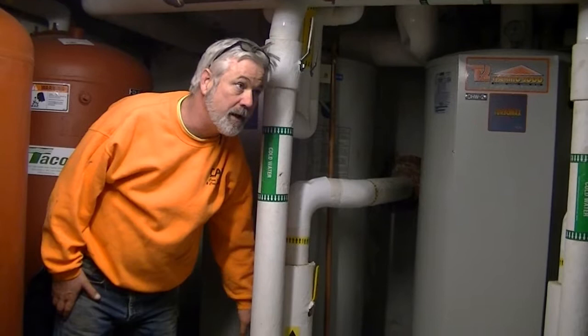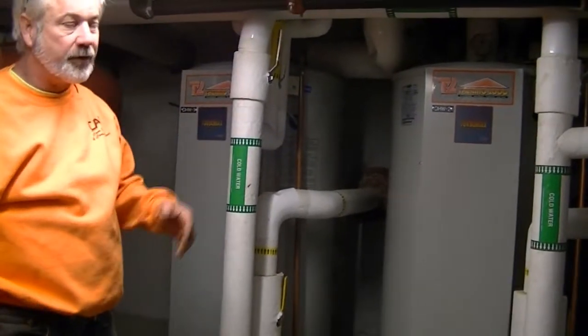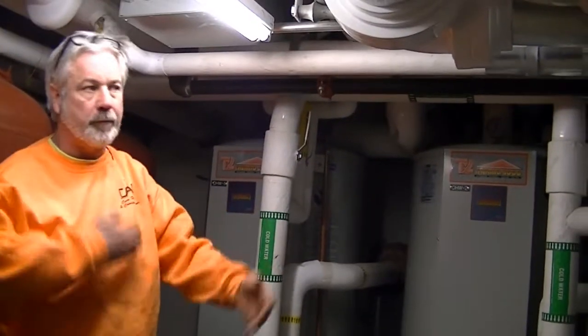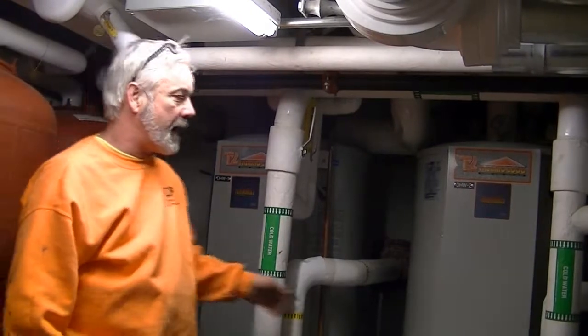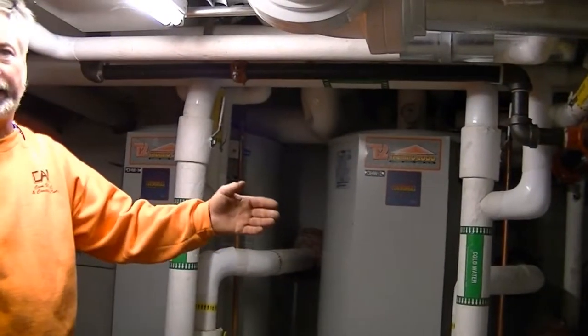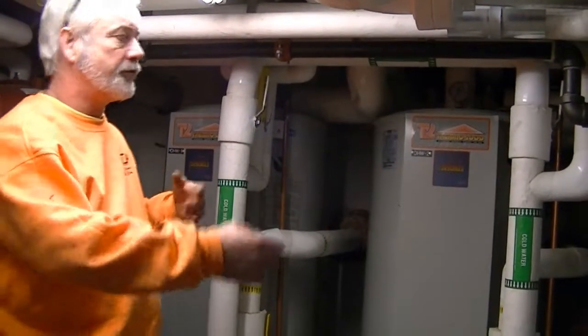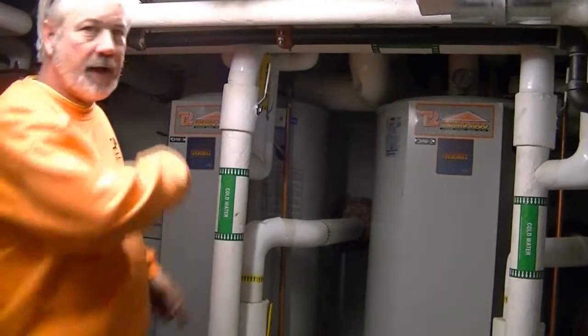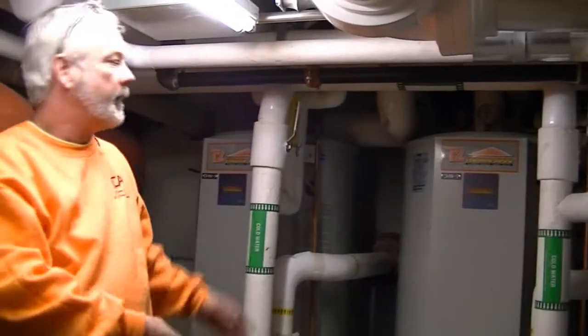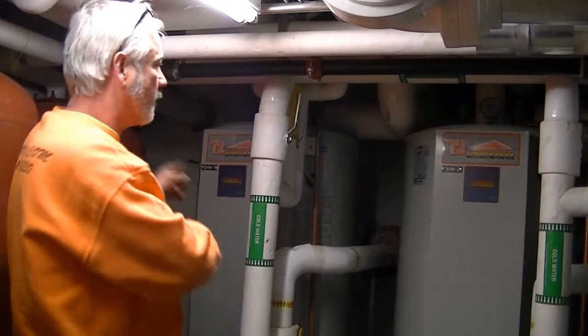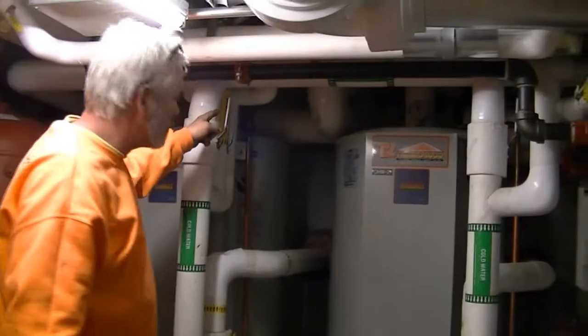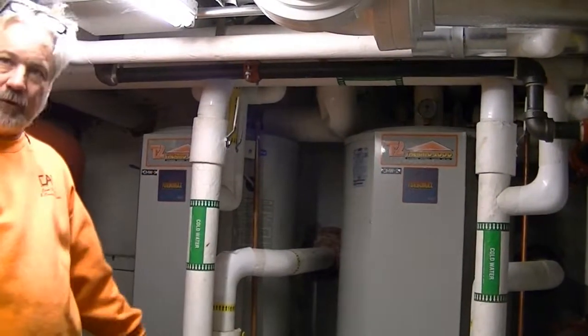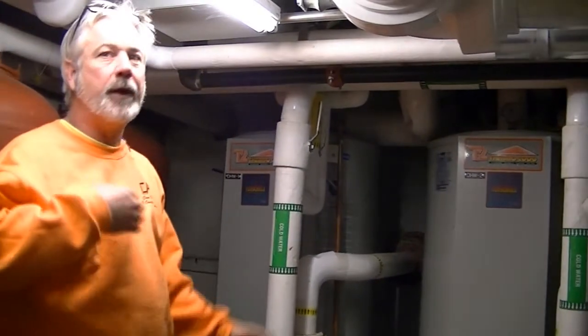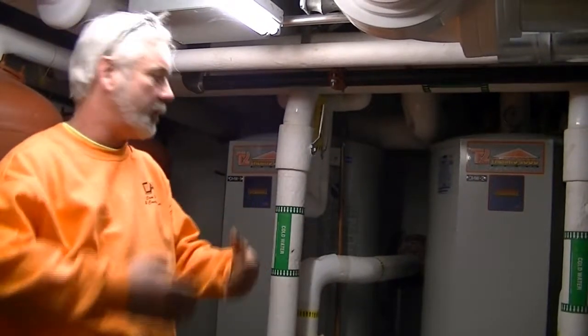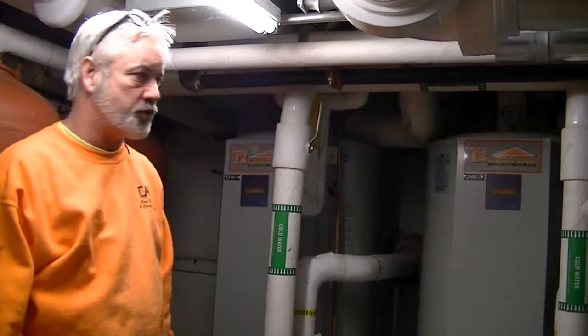You have to use them. The tanks have all been balanced, so they have the same amount of water going through them at all times. That way we can average out how the tanks are heating. Okay, they're also on a reverse return. First pipe in is the last pipe out. Okay? So as you're moving along, your supply hits the first tank first, but your return is the last return. That way you get even water flow, and then we put the balancing valves in to ensure that.